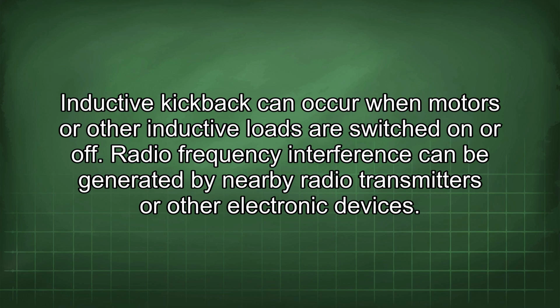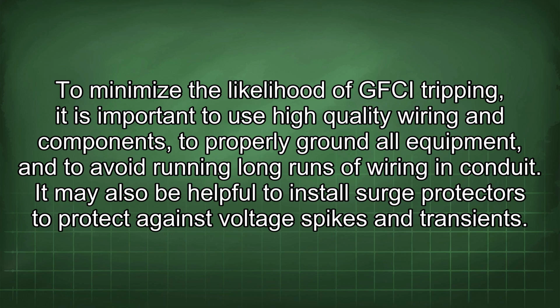Inductive kickback can occur when motors or other inductive loads are switched on or off. Radio frequency interference can be generated by nearby radio transmitters or other electronic devices. To minimize the likelihood of GFCI tripping, it is important to use high-quality wiring and components, to properly ground all equipment, and to avoid long runs of wiring in conduit. It may also be helpful to install surge protectors to protect against voltage spikes and transients.